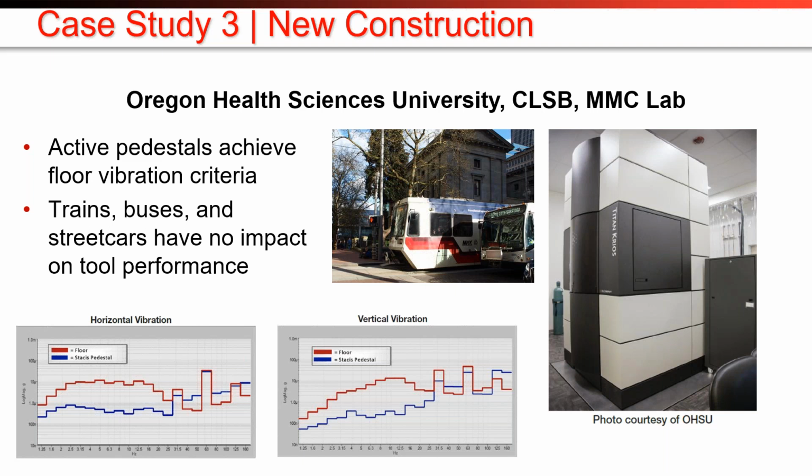So what they're able to do, with this clean approach, is achieve the floor vibration criteria of the instruments. And basically, they haven't been able to see any vibration artifact from any of the city activity, including the trains when they go right by. They see absolutely nothing. So it's been very successful.